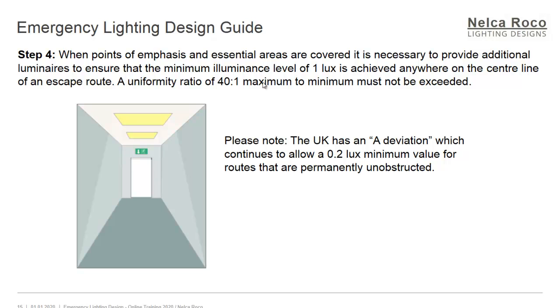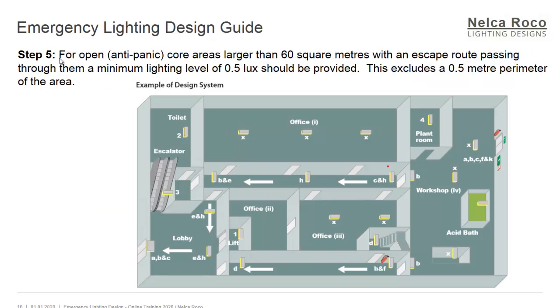Step 5: for open or anti-panic core areas larger than 60 square meters with an escape route passing through them, a minimum lighting level of 0.5 lux should be provided. This excludes a 0.5-meter border around the perimeter of the area — meaning you can offset the calculation surface from the wall by 0.5 meters. On the next video I will explain how to do that calculation, as it is better demonstrated in the software. For the open area, 0.5 lux is the requirement.